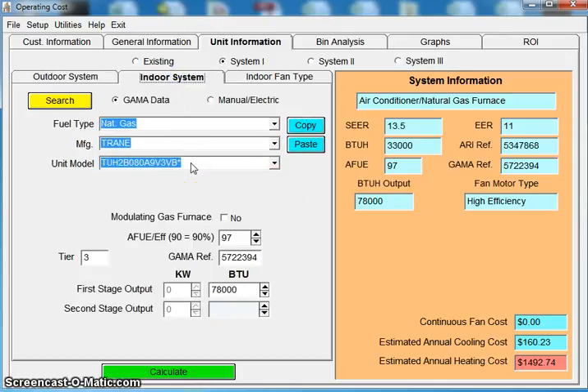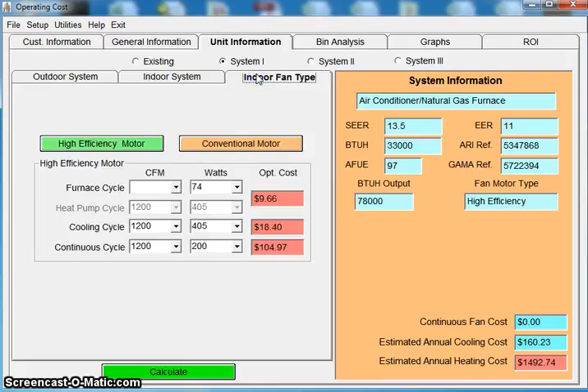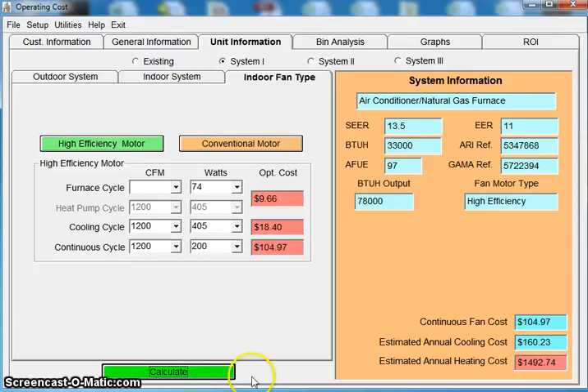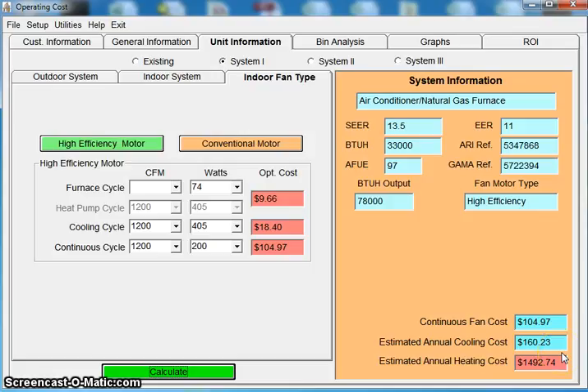On my indoor system, I've chosen a two stage variable speed gas furnace. My indoor fan, when I choose that furnace, it already knows whether it's variable speed or not. The program picks up that data. You click calculate. And that first system that I've proposed to them has now shown a significant savings. And that's just a basic 13 SEER air conditioner with a two stage furnace.